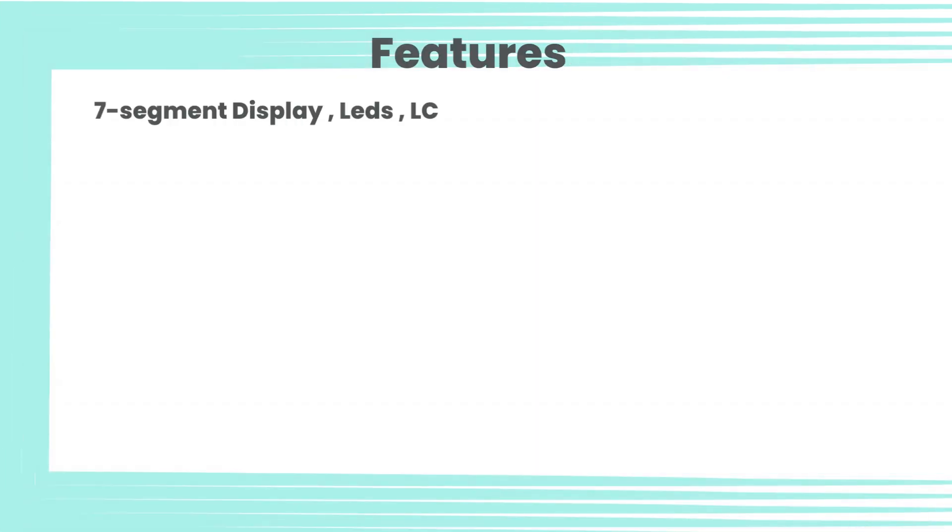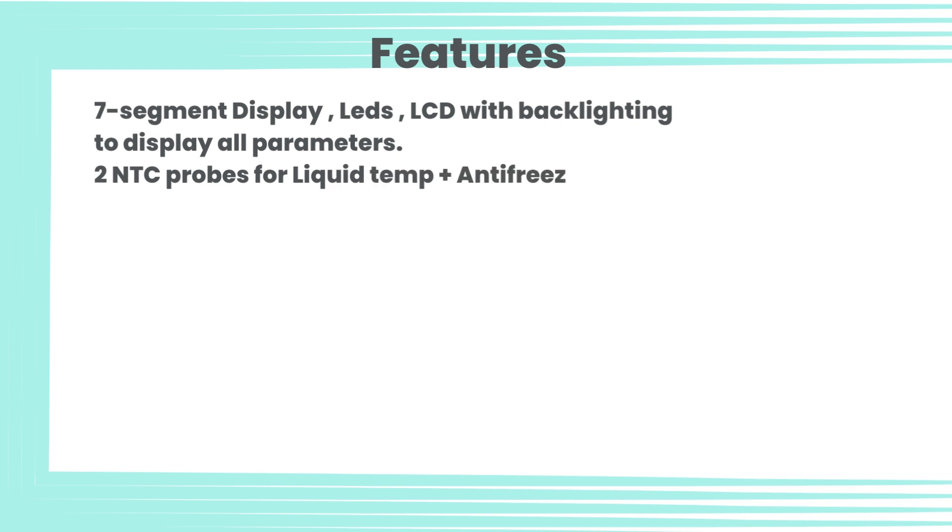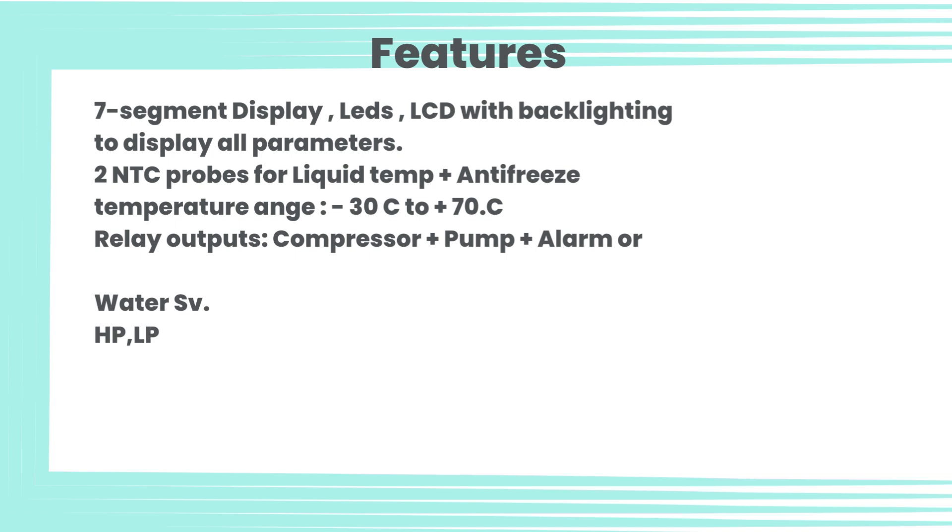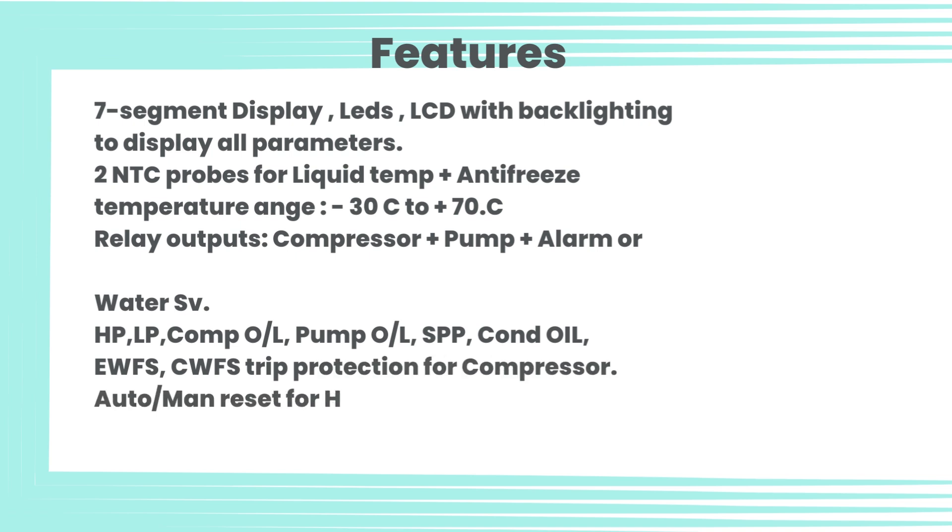Features: 7-segment display, LEDs, LCD with backlighting to display all parameters. Two NTC probes for liquid temp plus antifreeze. Temperature range minus 30 degrees Celsius to plus 70 degrees Celsius. Relay outputs: compressor plus pump plus alarm or water SV. High pressure, low pressure, compressor overload, pump overload, SPP, condenser overload. EWFS, CWFS trip protection for compressor. Auto/manual reset for high pressure, low pressure, and antifreeze. Last 10 fault history.